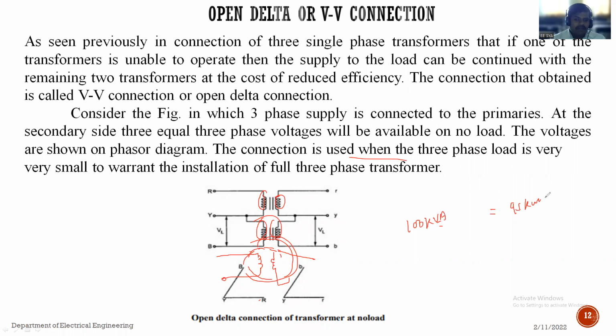That condition we are not able to use, but we are able to use it where the load on the transformer is small. Suppose a 100 kVA transformer has a load of nearly 60 kVA, or up to 50 kVA. We are able to use this delta connection, and if any one of the transformers is burned out, the remaining two transformers are able to continue the supply. That means continuity of supply can be maintained, with reduced efficiency.